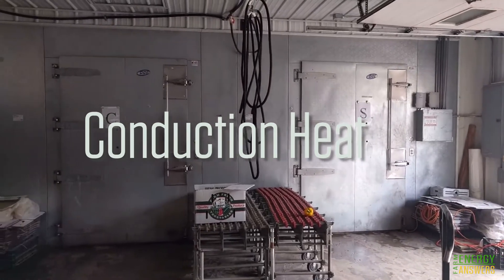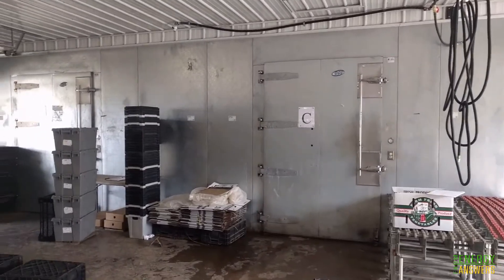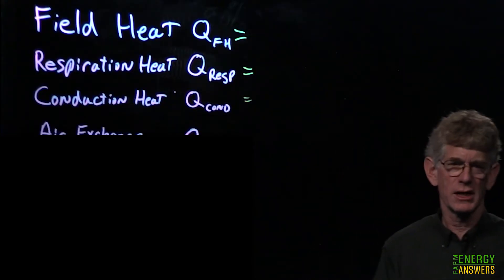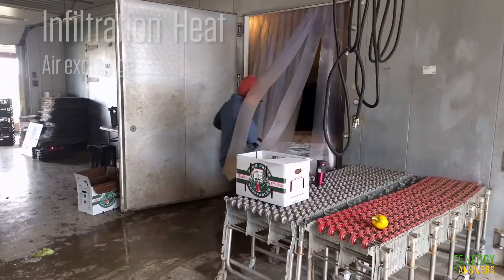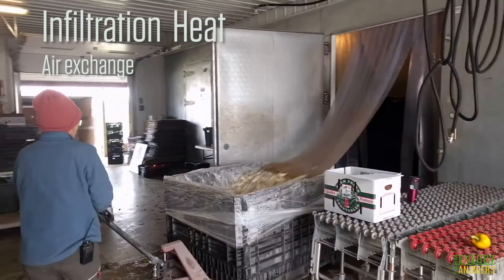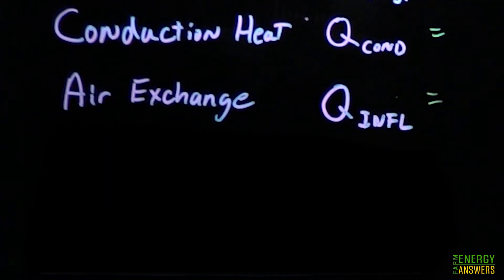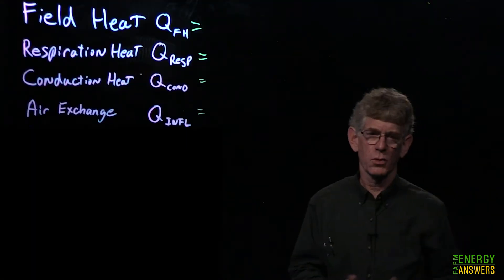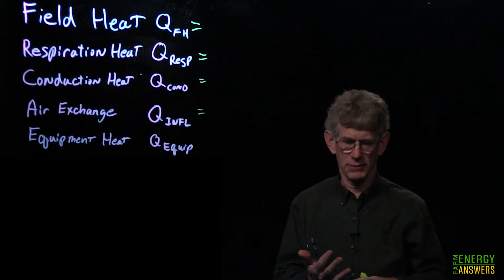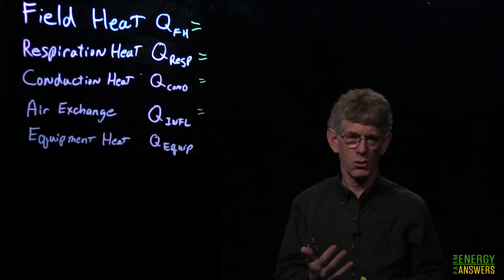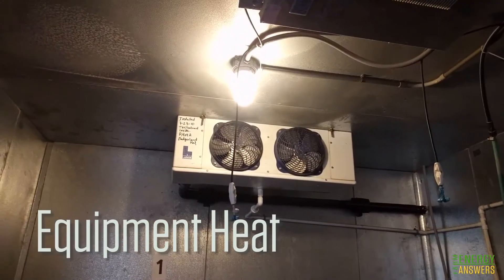Next is conduction heat — we have a box we're keeping at a certain temperature, so we have to add refrigeration to maintain that. Next is air exchange: every time we open the door to put produce in or pull it out, we lose cold air that's replaced by warm air we have to cool — we call that infiltration heat or air exchange. Next is equipment inside the cooler: we have fans to move air across the refrigerating coils, and we also likely have lights and possibly a fork truck.